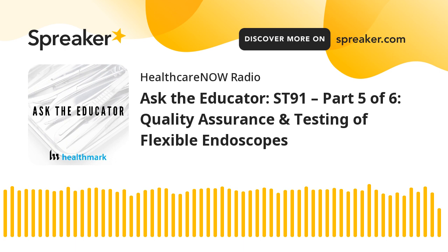But automated cleaning can go another step further. You could be talking about automated cleaning steps in an AER. So a lot of the AERs on the market today now have additional cleaning steps embedded into their cycle. So automated cleaning can also mean monitoring those steps of what is performed in the AER to ensure that that's happening. And you can do that through visualization. You can do that through flow verification. There are some products on the market for that, depending on the system that you have.